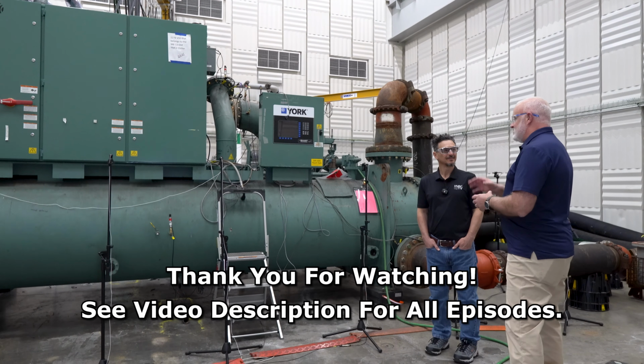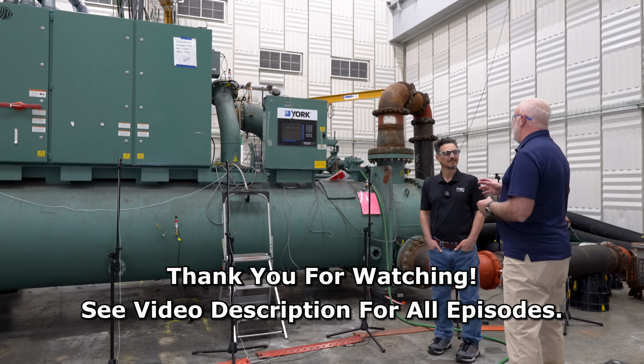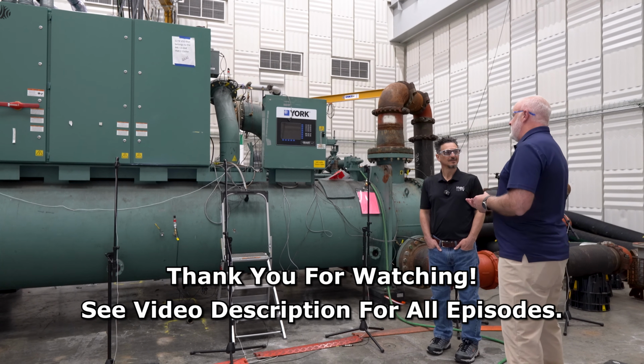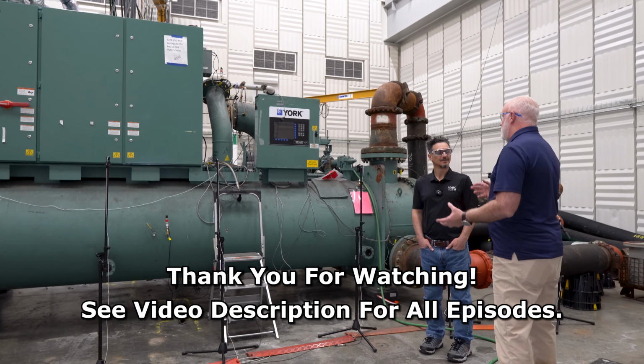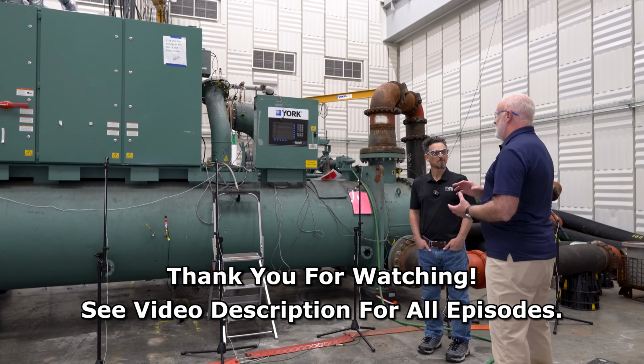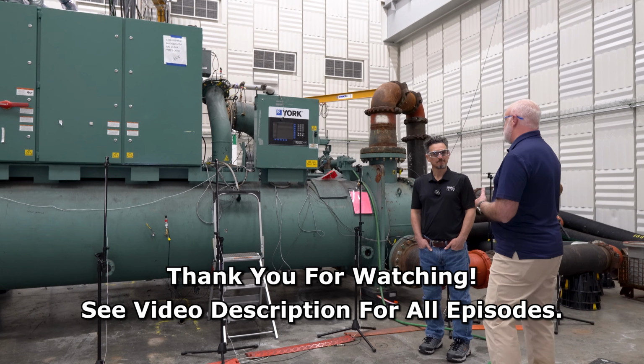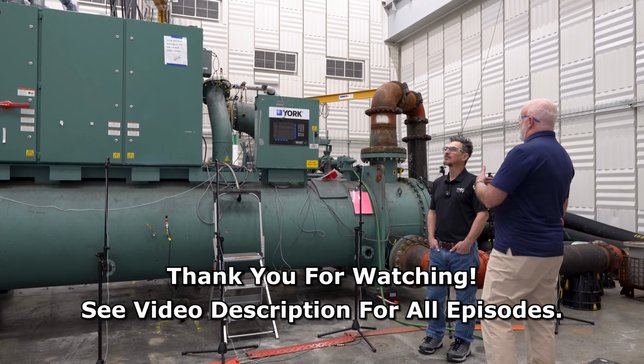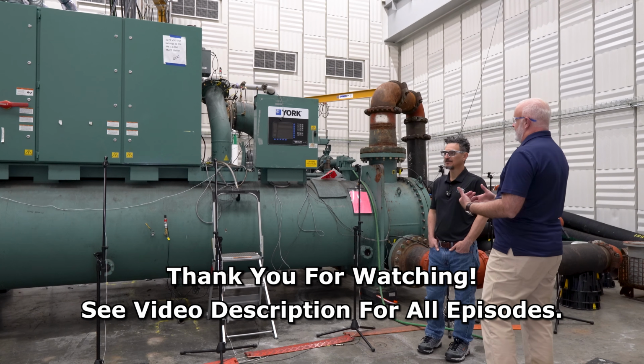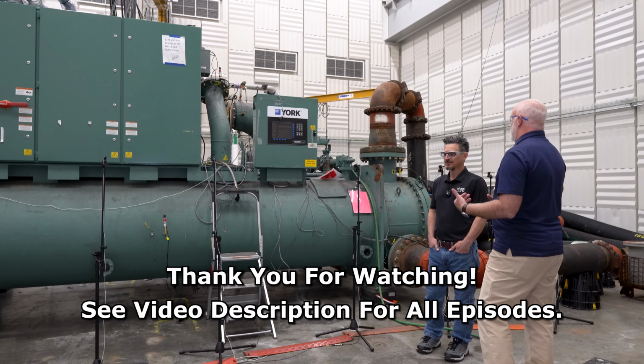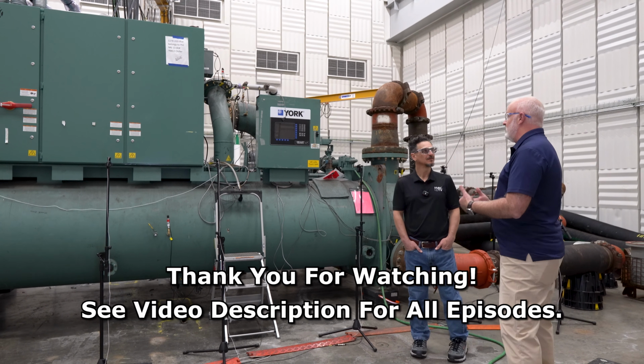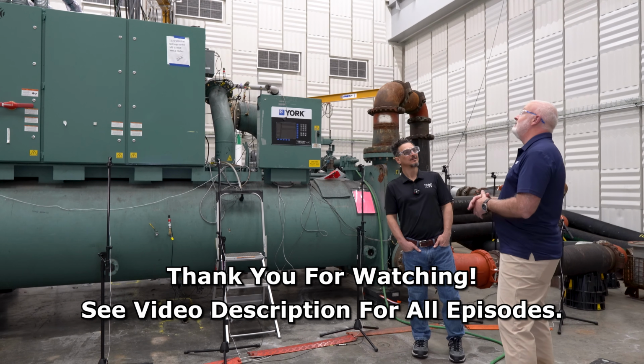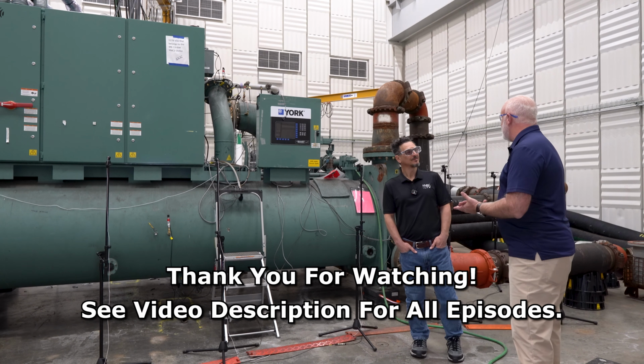It allows us just to tweak this, and that's a little different than what you may have seen in strictly component-only testing. Here we're going to make an adjustment based on what we measured that we expect to have an impact when we bring it back and reinstall it on this chiller and operate it again. So, yeah. Pretty cool, isn't it?